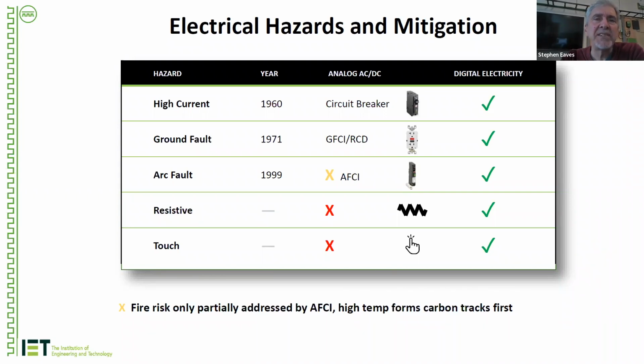And it's very difficult to detect that fault. It's not something that shows up as high current. It's not high enough current to trip the circuit breaker, and there's really no ground fault involved. It's just a poor connection. So the systems in packet energy transfer, because we're comparing very minute amounts of electrical energy in these packets, can tell whether a single packet hasn't made it to the end of the line. And that's in elements of millijoules that I'm talking about. So digital electricity can detect resistive faults in the line, which is extremely important when you're installing using what in the US is called Class 2 or Article 725 installation practices, which are the same practices as Ethernet cable.